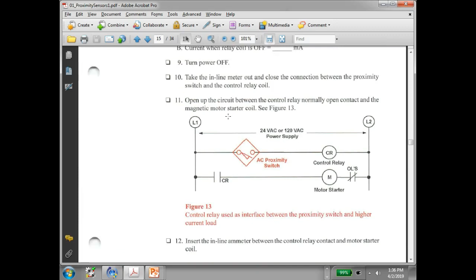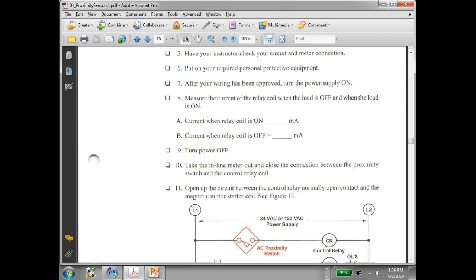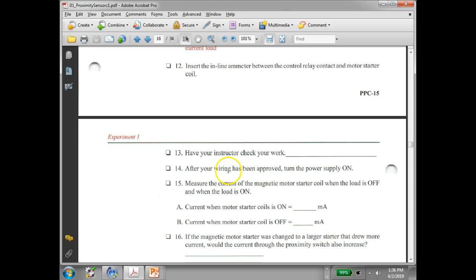Everybody okay? And then you're going to do what? After you've wired it and it's been approved, measure the current in the relay when the load is off. Measure the current when the relay is on, right? Take the inline meter and close the connection between here. Insert an inline ammeter, have the instructor approve. Measure the current of the magnetic motor starter, right? With what? With the motor on and the motor off. Are you okay there?